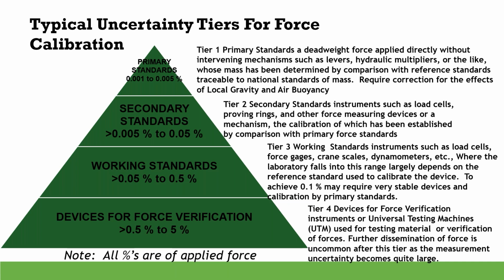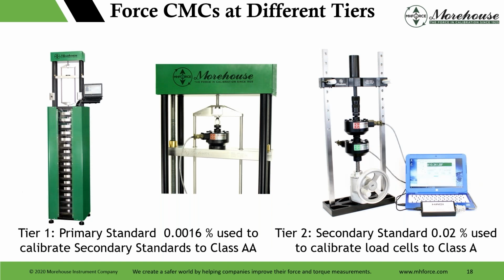So this is really contained in E74, and you can see they build it in such a way that you have ratios built into all of this. The end goal is to likely calibrate a 0.5% or 1% testing machine following these steps. Now, force is used everywhere, so the end goal could be to calibrate a sensor that goes in your car to detect if somebody's in the seat to deploy the airbag or not. That has much higher uncertainties than what I'm showing there. You just don't need to be that good. You just need to know if somebody's sitting in the seat or not.